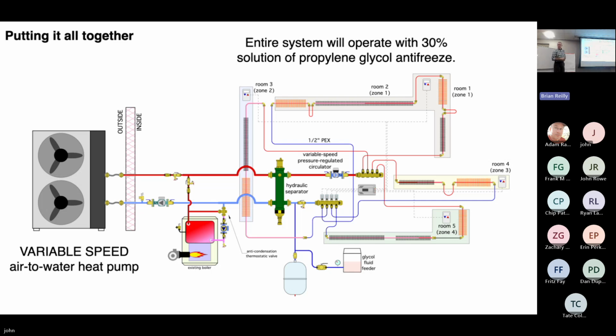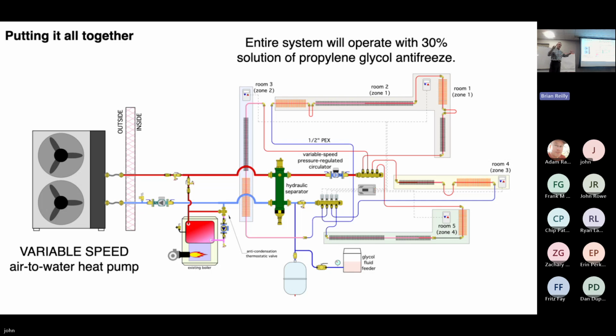So in this scenario, the whole system is glycol. Yes, in this scenario, the whole system would be glycol. So then the fan coil units would be glycol as well. Yeah, they would be. That's not a problem, but I tell you, it's actually a benefit if you're doing an air handler, especially if the air handler's in the attic. You have essentially distributed air conditioning. Yep, a coil, a blower, and a cabinet. With ducting. Right, with ducting.